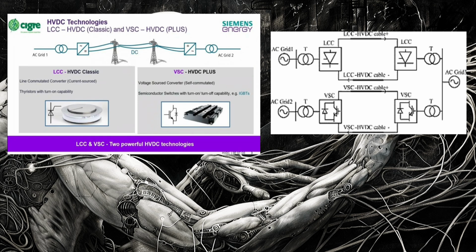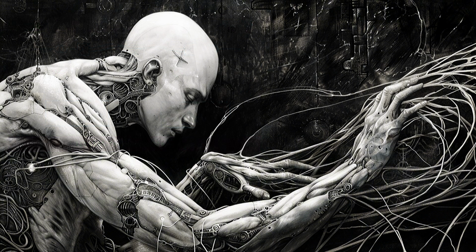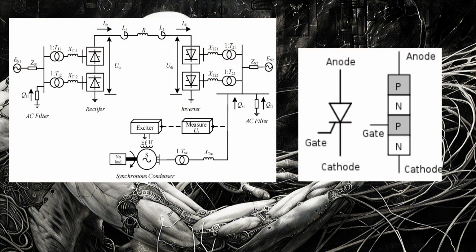LCCs were the original converter type used for the very first HVDC links. As such, they are commonly referred to as HVDC Classic. VSCs are relatively new technology and are commonly referred to as HVDC Plus. LCC, also known as a current source converter, uses a thyristor-based technology. The thyristor is a silicon semiconductor device with four layers of N and P type material acting as bistable switches, triggered on with a gate pulse and staying in that on condition until the next current zero crossing.